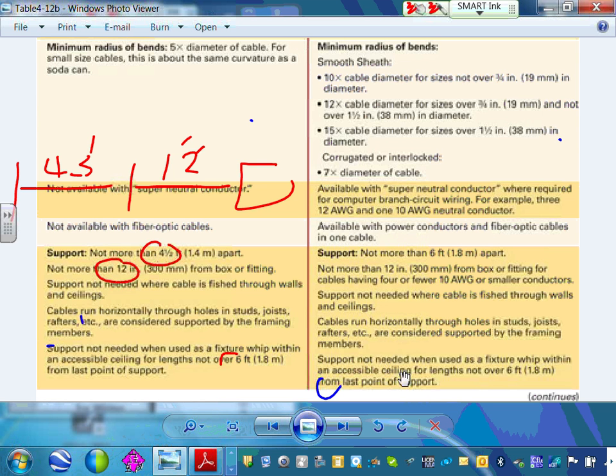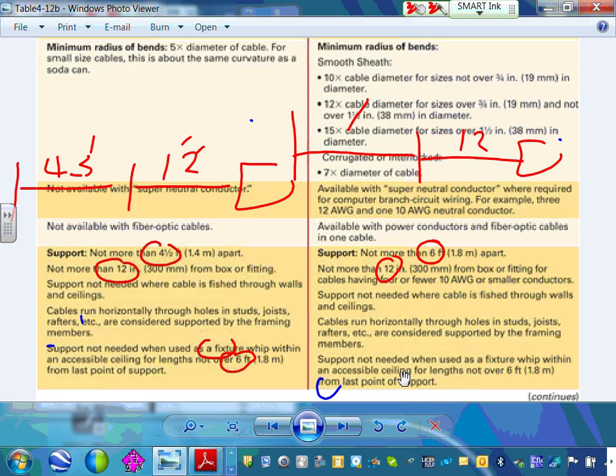Fixture whip, can you see that number 6 here, support for ceiling accessible length, that's your fixture whip. Can you guys highlight that one? So can I have 6 feet of it not supported, tied to a fixture? Bring it on. Okay, let's look at the support for this guy. Not more than, what's the support for this guy? 6 feet, 12 inches. So 12 inches and in between 6 feet. So anyway, you can see where the support is different even.